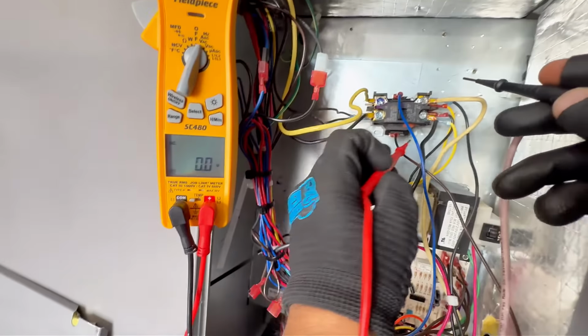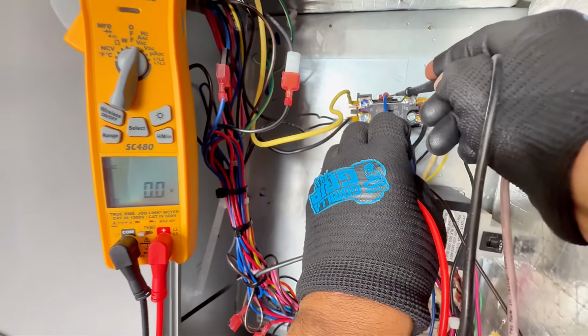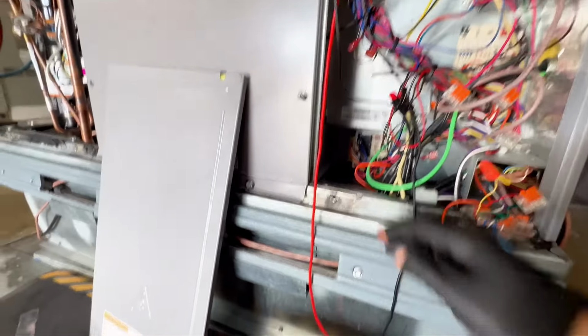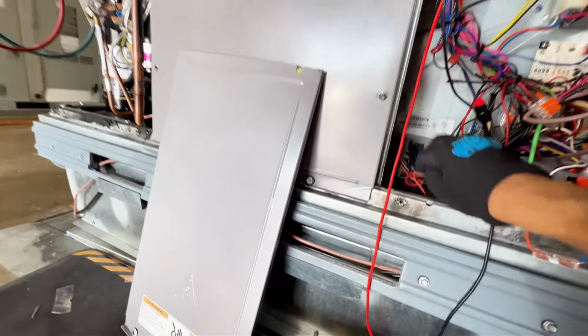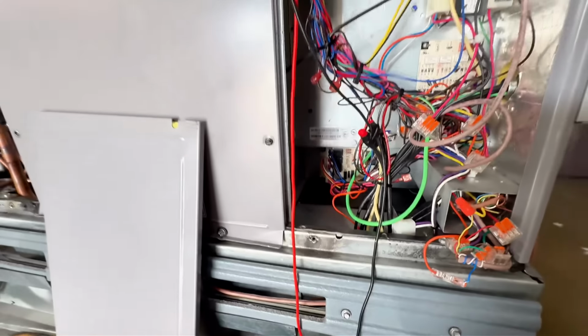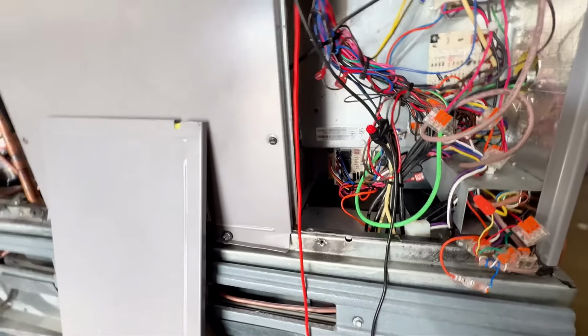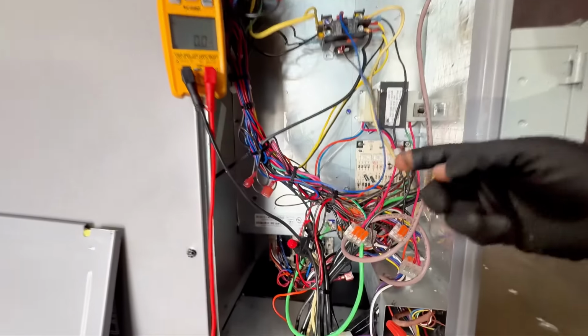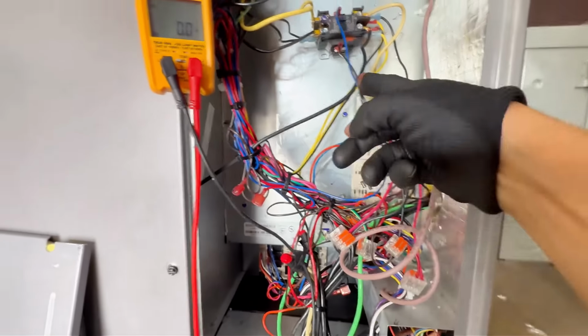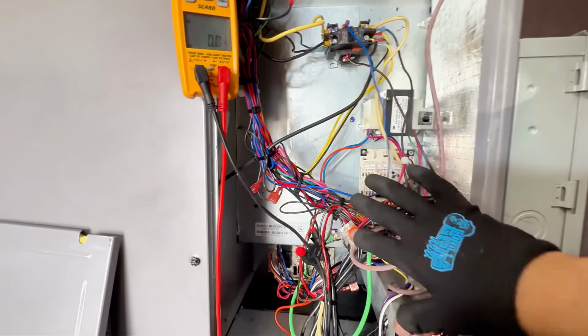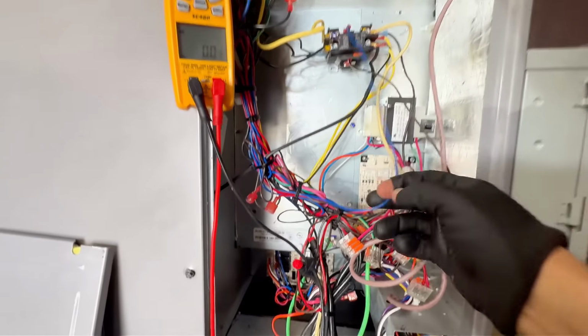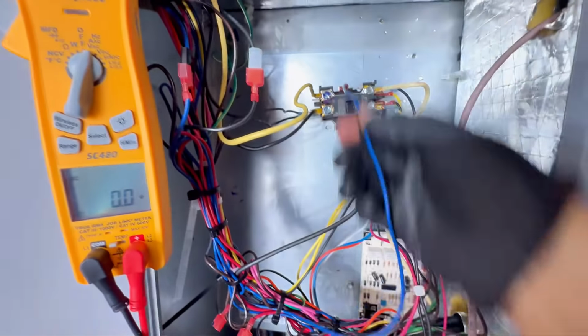The problem is that right here, my contactor coil, when checking it, I'm getting 0 volts. So let me see what he did. Okay. I think I figured it out. So this brown one here is my common. My brown goes to all my commons. They're already all there. My blue one, this is a problem. I'm not getting 24 volts here.